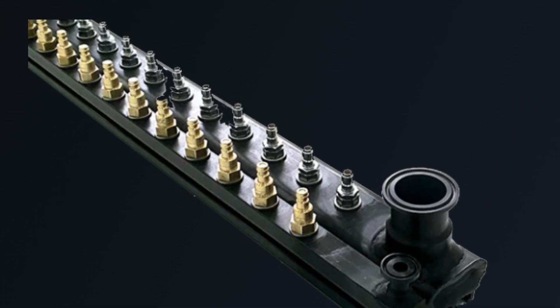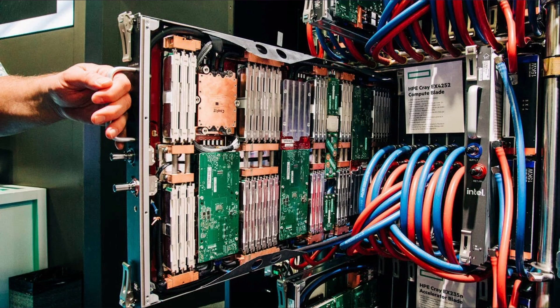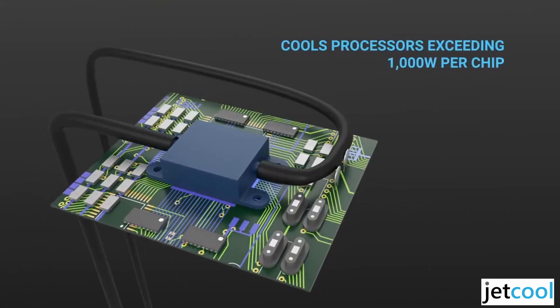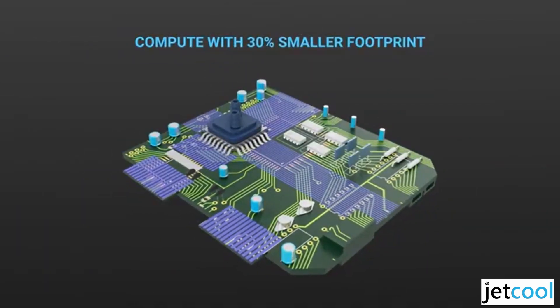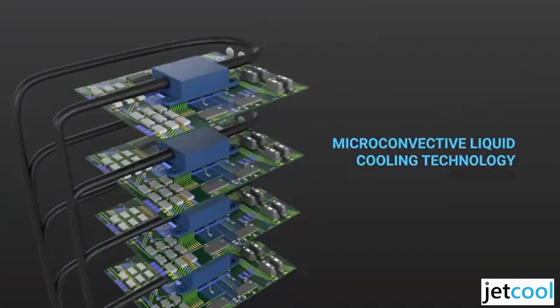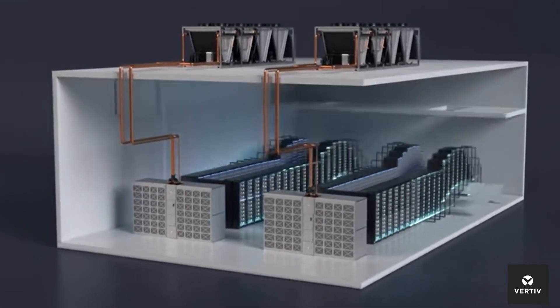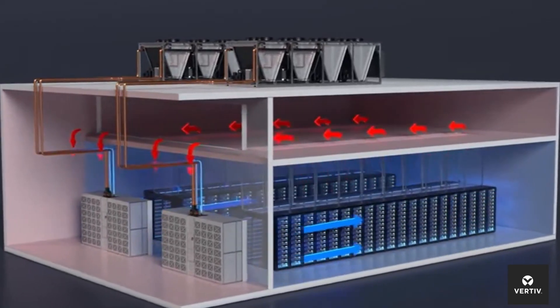The basic idea is pretty simple. Liquid is piped into manifolds within the rack, and each server has a small dripless connection to hook up to each of the hoses. These dripless connectors are designed to prevent any leaks whatsoever. Inside the server, there are small pipes that carry liquid directly to the CPU or a cold plate on it, and sometimes to the GPU. Often there's still some air cooling involved for other components on the motherboard, but liquid handles often 60% to 80% of the heat removal. The liquid enters the server cooler than the components, draws the heat away, and leaves hotter, having absorbed that heat. Importantly, the cooler liquid might still feel hot to the touch — it only needs to be cooler than the components it's actually cooling.